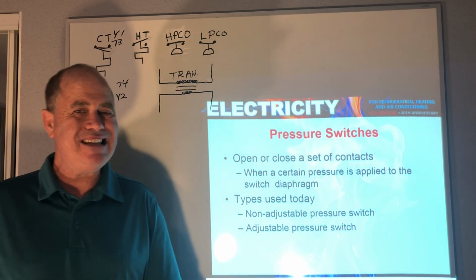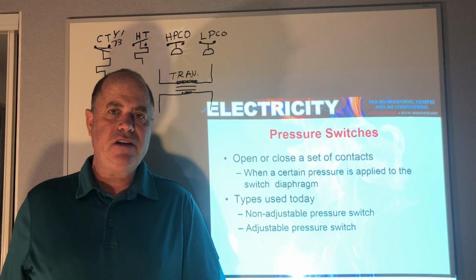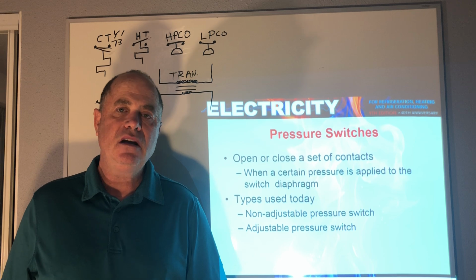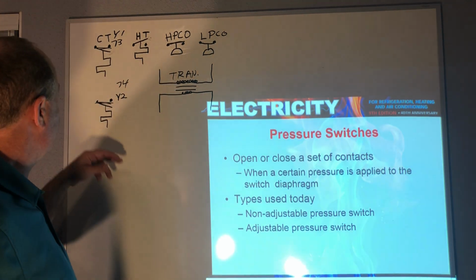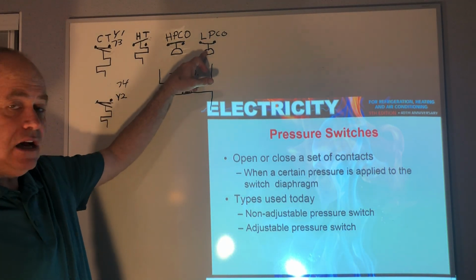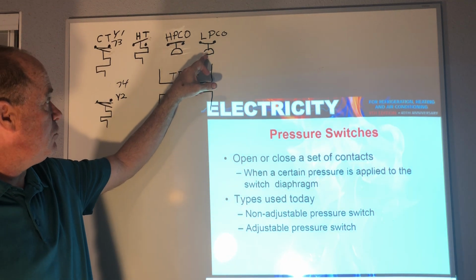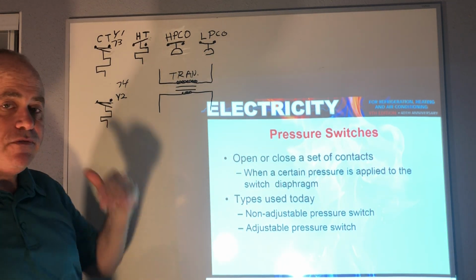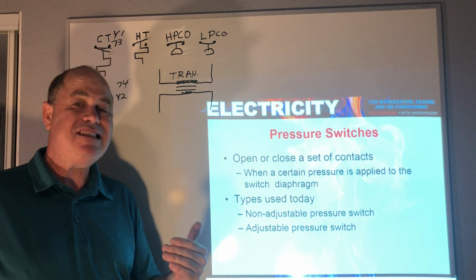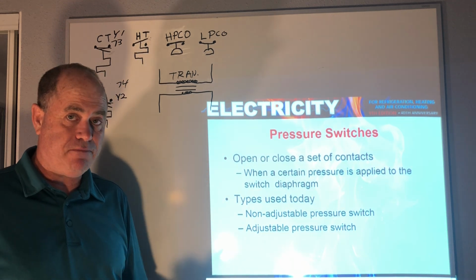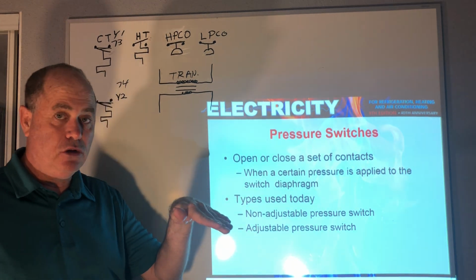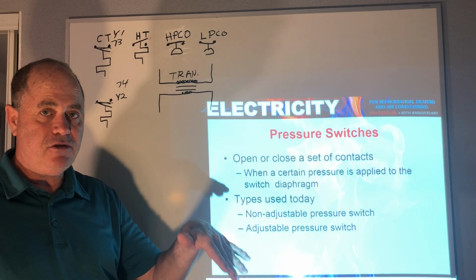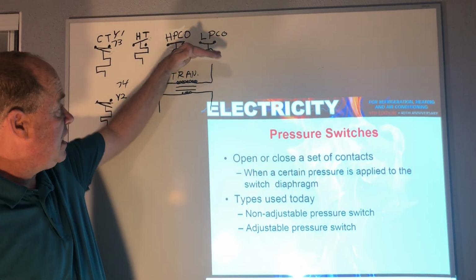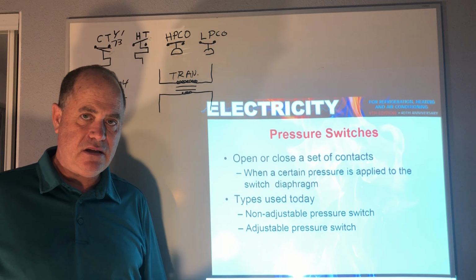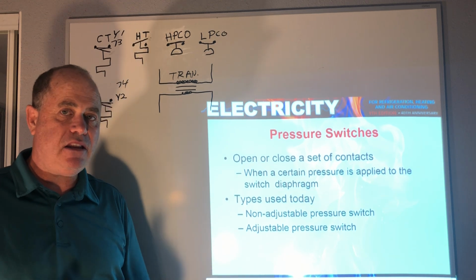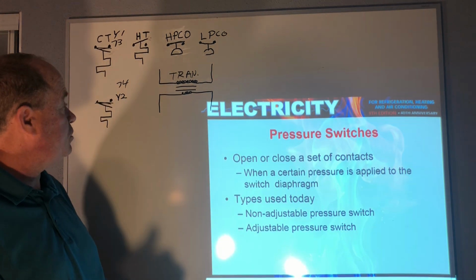Now pressure switches, very extensive. I'll just give you the basics on this. The most common type of pressure switches would be a low pressure cutout here, and this is the electrical symbol for that, where if the system gets low on refrigerant and the low side pressure on the suction line gets too low, we don't want the system to run without refrigerant. The contact opens up, breaks the circuit as a safety, and the compressor is then protected.